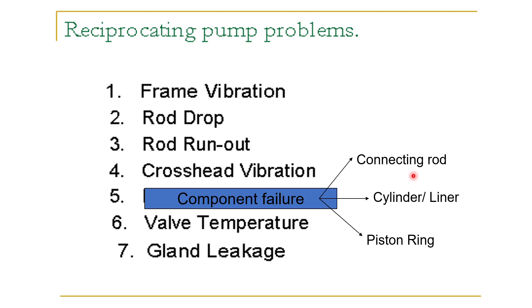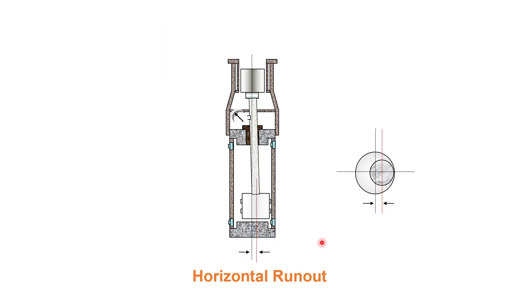Now let us look at some problems in the reciprocating pump. One problem is vibration of the main frame at different points. Then there is rod drop and rod run out — which we will see next. There are also crosshead vibrations, component failures including connecting rod, cylinder, liner, and piston ring failures. Sometimes valve temperature may be a problem, and there can also be gland leakage.